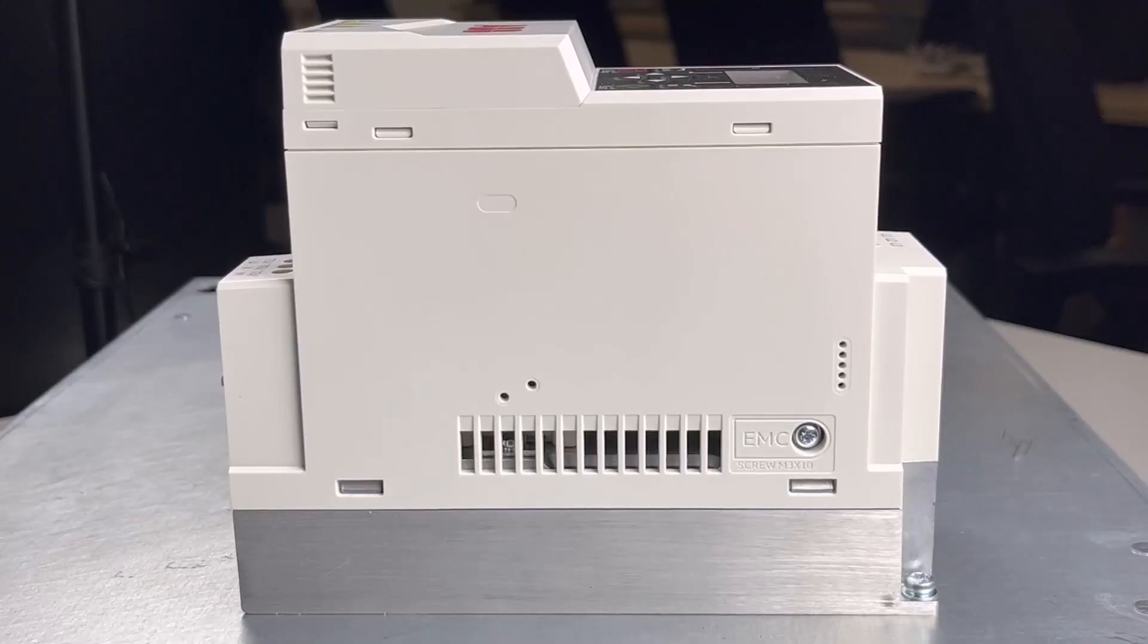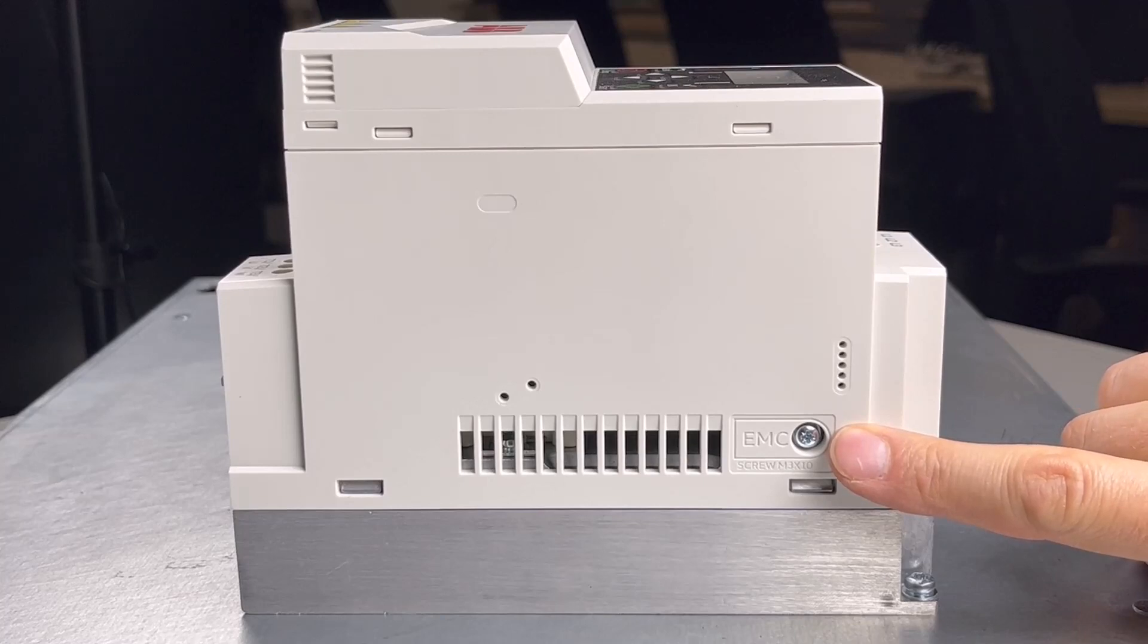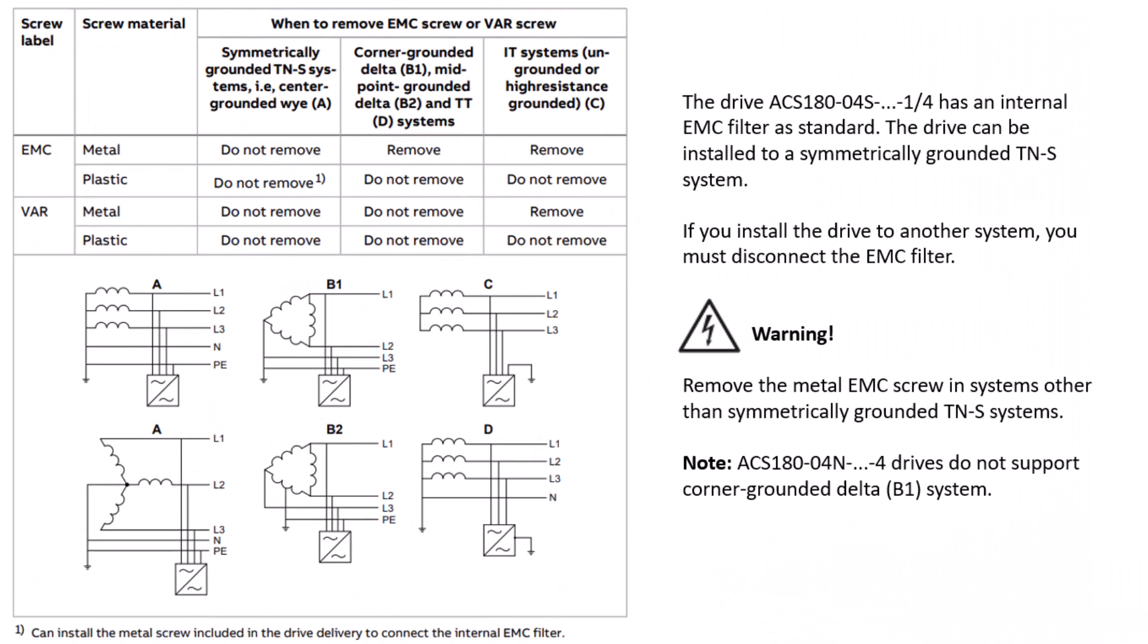The ACS-180-04S-1 and -4S have an internal EMC filter standard. You can install the drive to a symmetrically grounded TNS system. If you install these drives to any other system, you must disconnect the EMC filter prior to power up. Please see the hardware manual for information on how to determine the grounding system of the electrical power network.